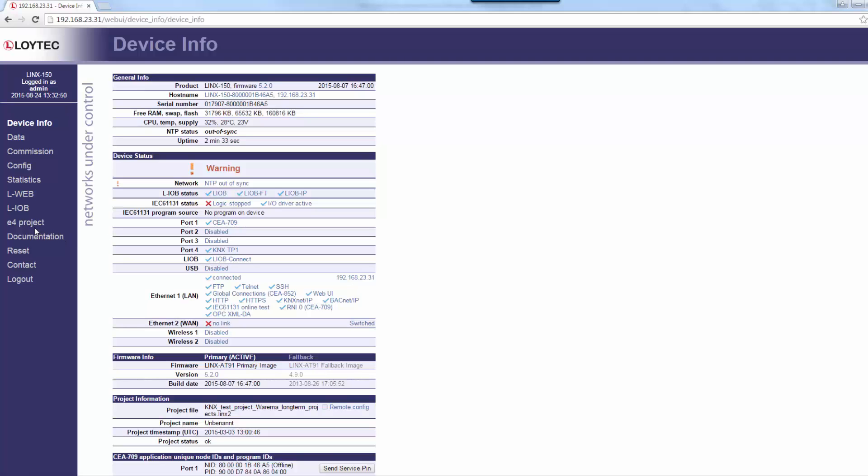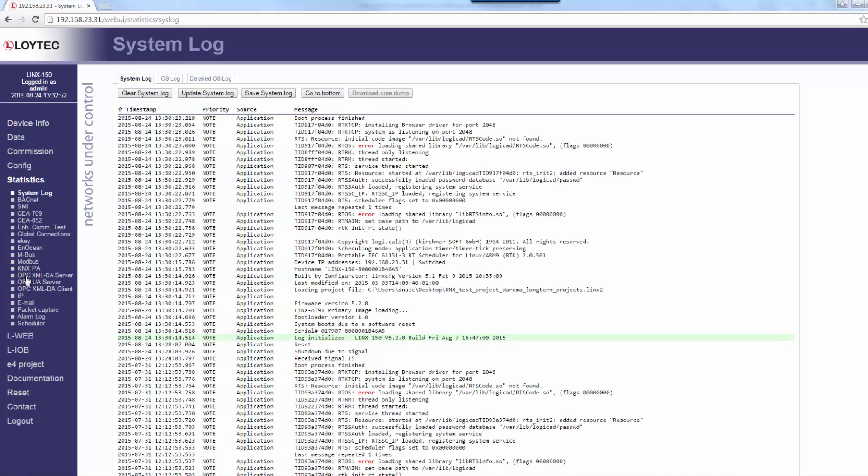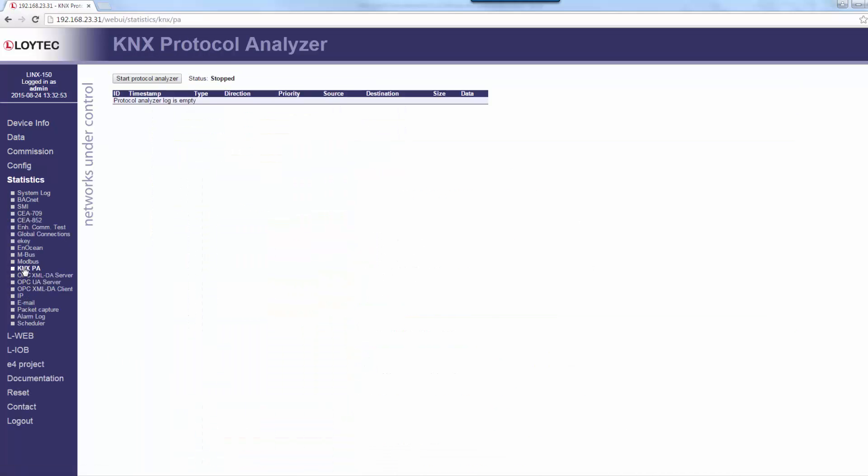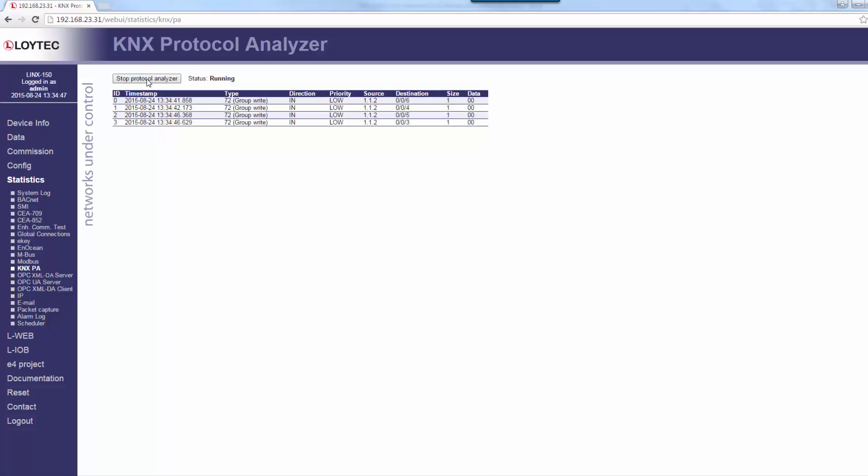Devices that support the KNX protocol now have a built-in protocol analyzer. It can be accessed through the KNX statistics web interface and allows starting, stopping and storing protocol logs on any of the KNX interfaces. If the analyzer is started, an automatic refresh is performed every 5 seconds.